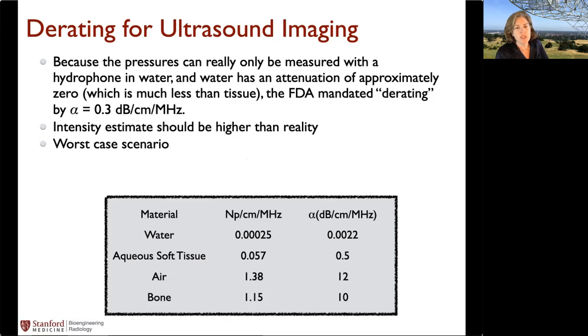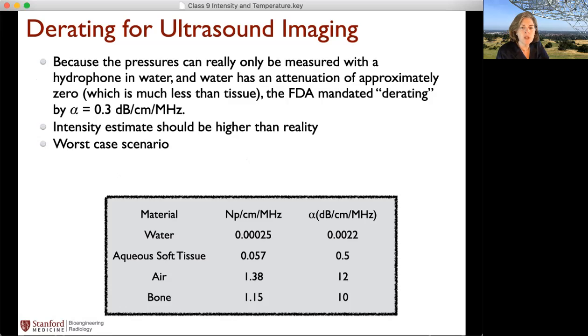All right, so you scan around and you measure what the pressure is. You can convert that, of course, into intensity. For ultrasound imaging, whenever they're estimating what the intensity is deep inside the tissue, they have to take those measurements that they might get in a water bath and then derate them for the situation that they're in. What they do is, for whatever the beam path is, so the length of the beam, they derate it with an attenuation parameter of 0.3 dB per centimeter per megahertz.